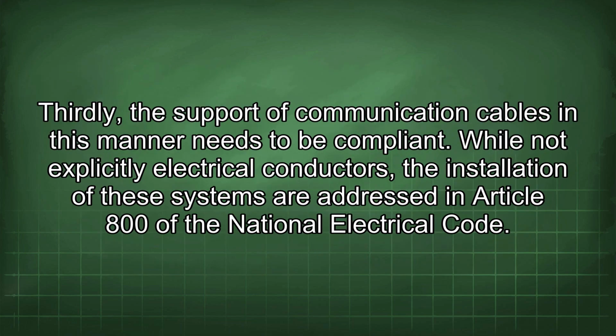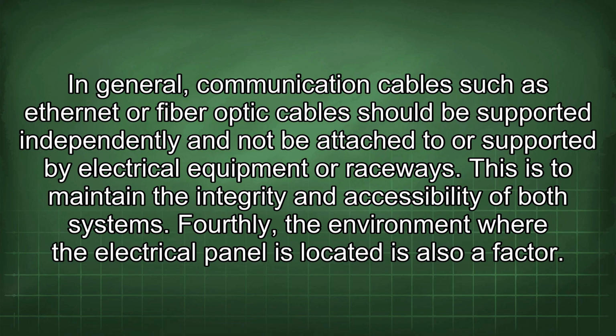Thirdly, the support of communication cables in this manner needs to be compliant. While not explicitly electrical conductors, the installation of these systems are addressed in Article 800 of the National Electrical Code. In general, communication cables such as Ethernet or fiber optic cable should be supported independently and not be attached to or supported by electrical equipment or raceways. This is to maintain the integrity and accessibility of both systems.